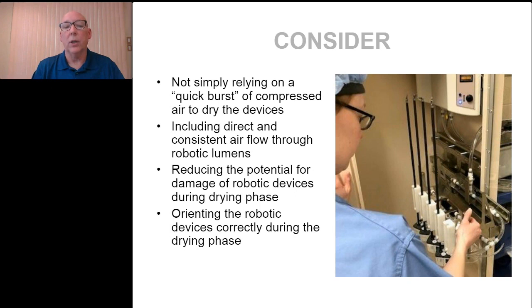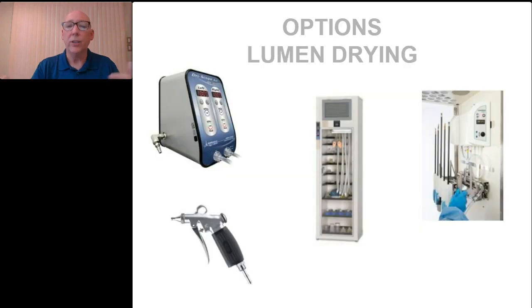And also consider not simply relying on a quick burst of compressed air to dry your devices, including a direct and consistent airflow through your lumen devices, and reducing the potential damage that may occur if those devices are just lying around on shelves. And making sure that the devices themselves are oriented properly during the drying phase. There's lots of options for lumen drying that you may have purchased or are using in your department, whether it's drying cabinets, air guns, other lumen drying devices for scopes, as well as a new lumen drying device itself.